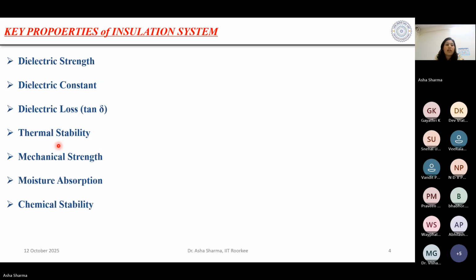The next is chemical stability. If I talk about chemical stability, we can think about transformer oil, which we use as a liquid insulating material in the transformer. It serves a cooling purpose as well as insulation. But let's say some fault occurs, some incipient fault within my system, within the winding. Obviously, if a fault occurs, there will be some heat generation, and the oil loses its property. So to some extent, it is allowed that the transformer oil is okay, but after that we can't reuse it. That's why we have to take care of the chemical stability of my insulating system, in context of the liquid insulation or the transformer oil.